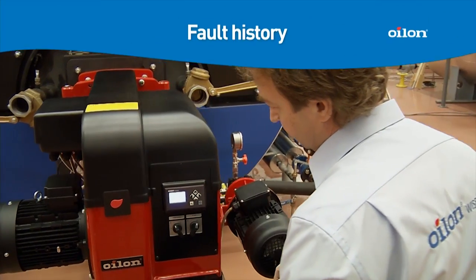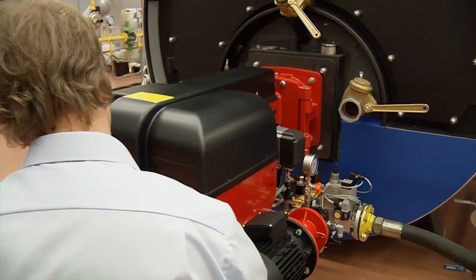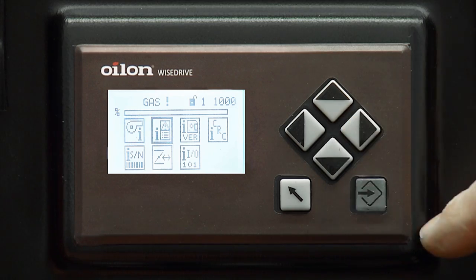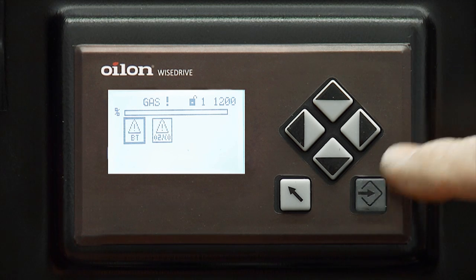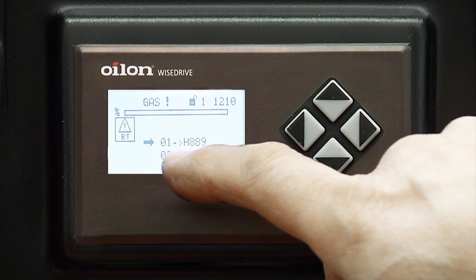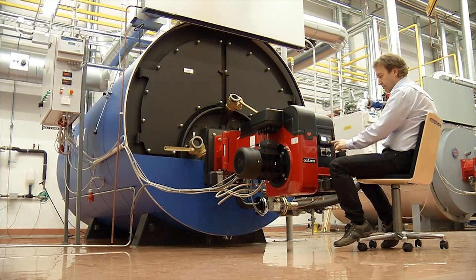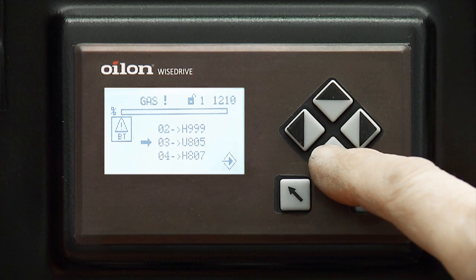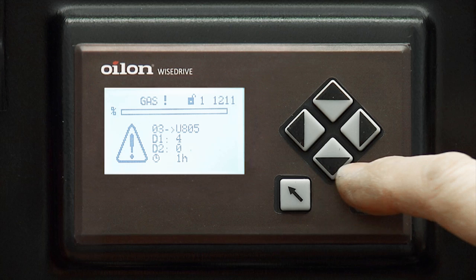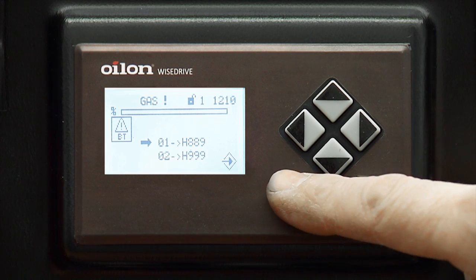The fault history menu is important for all burner operators. The error code in the history list will indicate the fault that has stopped the burner. Access the menu by pressing enter. You will find an icon for the control unit and pressing enter there again will open the fault history. The display shows the last 10 faults. You can browse through them and, if you require more information on a specific fault, just press enter to see the details. Detailed information on the error codes can be found in the manual. Pressing back repeatedly will take you back to the main menu.